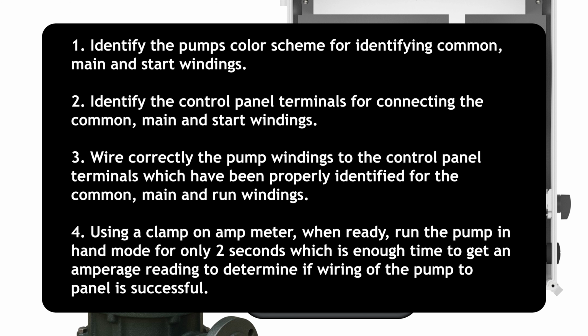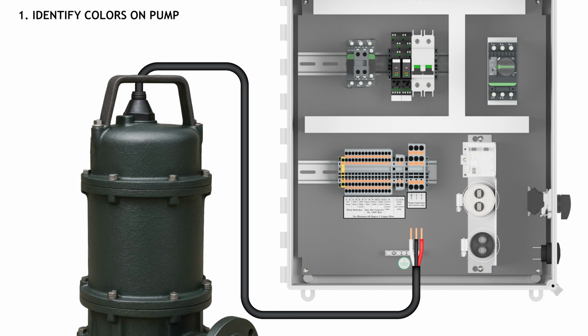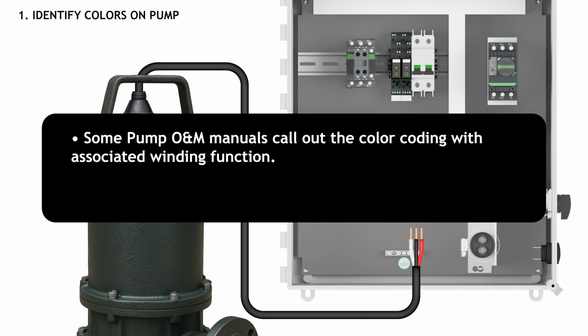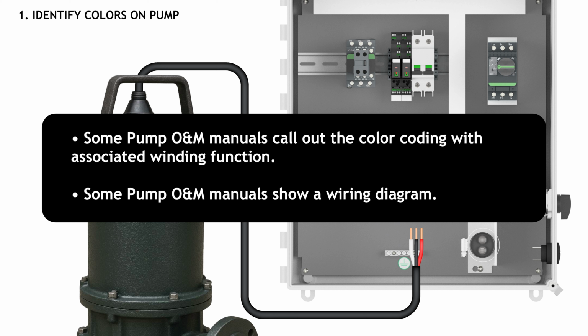to determine if wiring of the pump to panel is successful. Step 1. Identify pump colors for identifying common, main, and start windings. Some pump manufacturers will call out, for example, black equals common winding, white equals main winding, and red equals start winding, and will also give the ohm values of each winding that helps with installation and troubleshooting. Other pump manufacturers may show a wiring diagram showing how the capacitor kits are wired to which color pump wires, but make no mention which wire color is the common, main, and start windings.